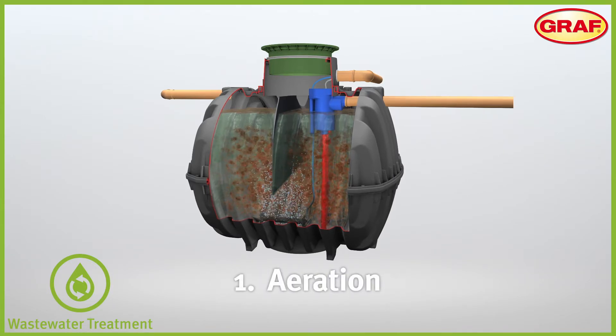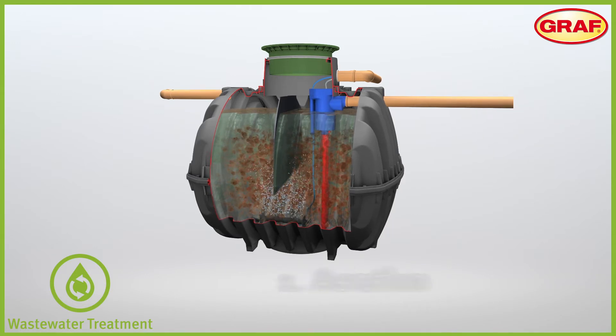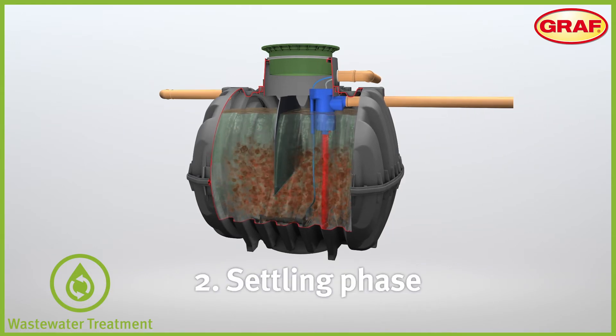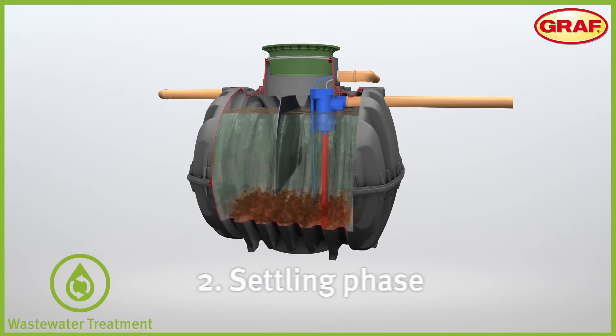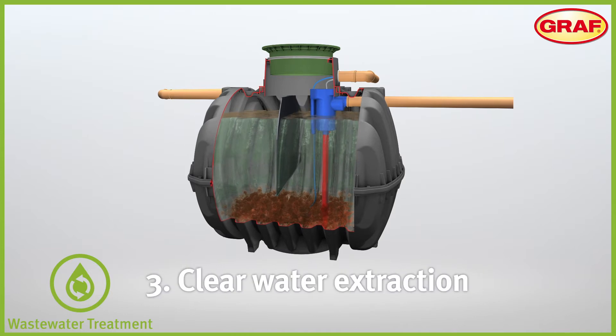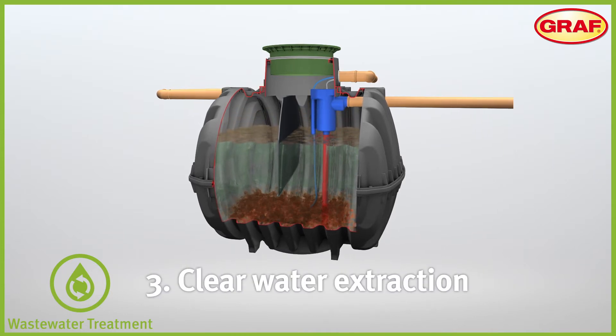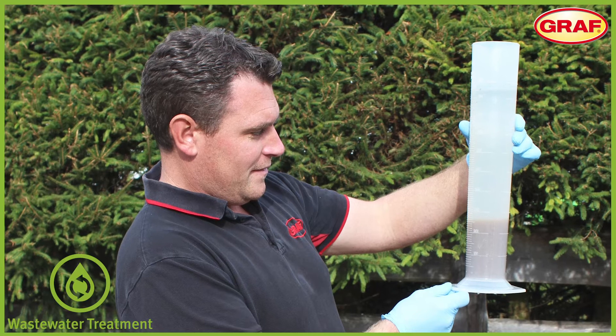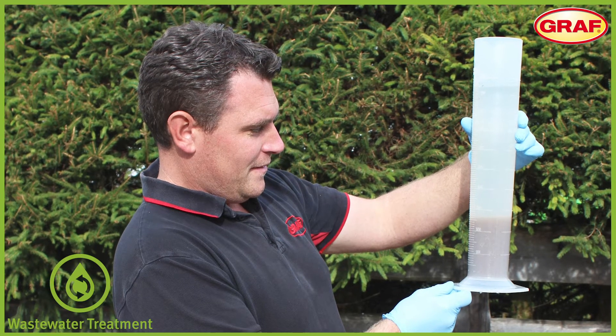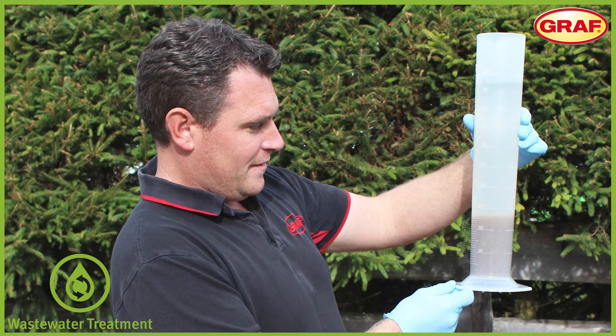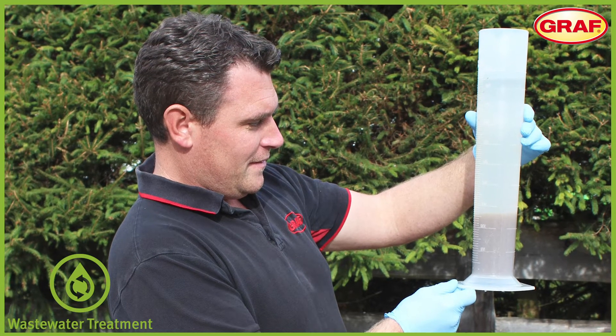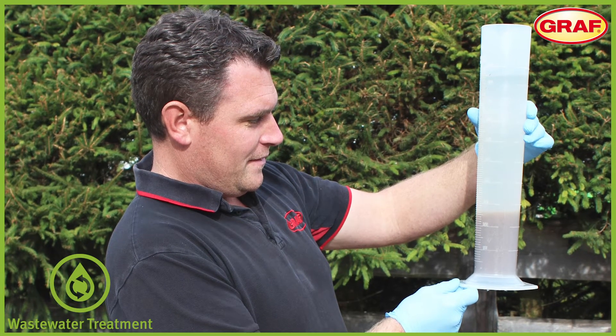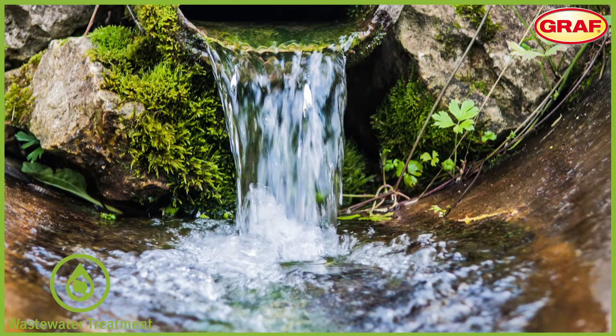The solids will be retained in the wastewater tank, leaving the treated effluent to rise to the top of the water level before being discharged out of the tank into a soakaway or a flowing watercourse if permitted. Sewage treatment plants are becoming more and more common throughout the UK because of the quality of effluent that can be discharged from the plant compared to old solutions like a septic tank or cesspool.